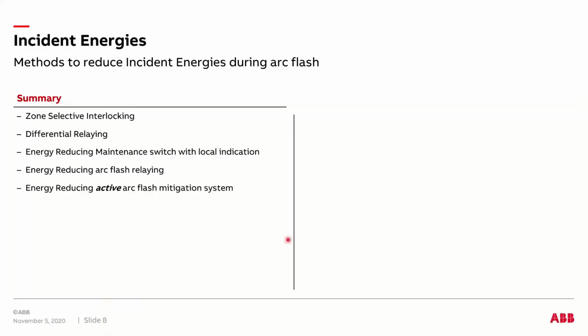So I have listed some of the methods that are most popularly used to reduce the incident energy levels during an arc flash event. One of them is very popularly known as zone selective interlocking, differential relaying, which is also well known, and the other one is a reduced energy maintenance switch. We call it reduced energy let through, REL.